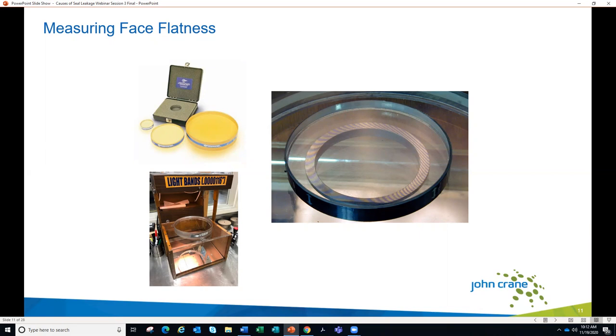The label on our light source shows the light bands called out for 11.6 millionths of an inch — that's actually one half of a light band of helium. Every half of a light band causes the interference. So if we're within one light band of flat, we would be within 11.6 millionths of an inch of being flat.